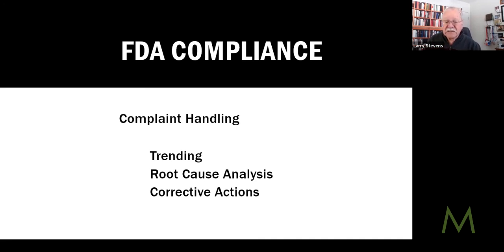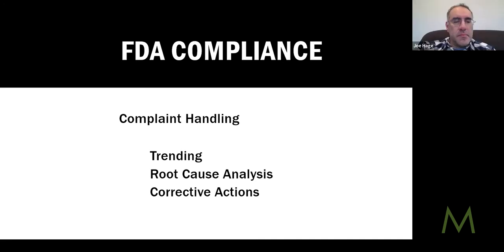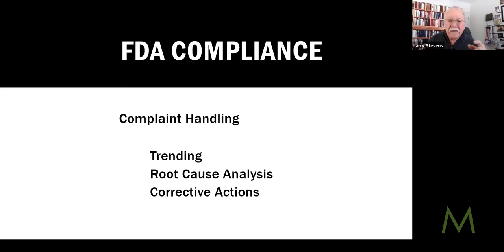Root cause analysis. Now, the key is that at some point you should try, on every complaint, to determine what caused it. Now, is it the root cause? Who knows? But if it's attributed to something that is a design issue, or a user error that perhaps can be fixed with changing the labeling, that needs to be linked to the root cause analysis. What do we need to do? And that default thing is the corrective actions.